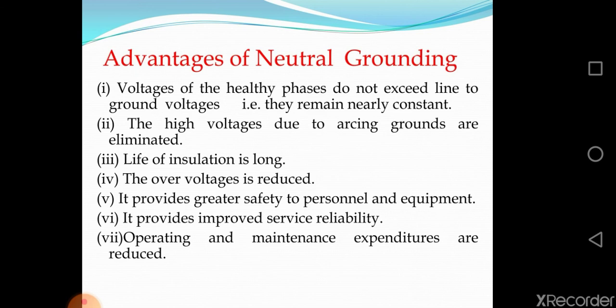Advantages of neutral grounding. Voltages of the healthy phases do not exceed line to ground voltages. With effective grounding they remain nearly constant. The high voltages due to arcing grounds are eliminated. Life of insulation is long. The over voltages are reduced. It provides greater safety to personnel and equipment. It provides improved service reliability. Operating and maintenance expenditures are reduced.